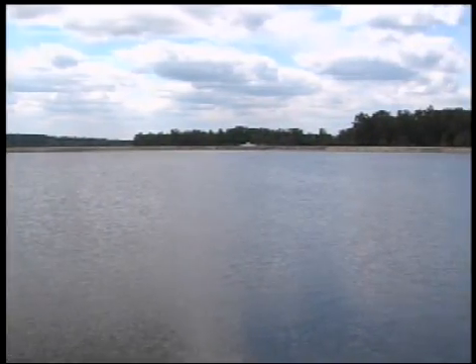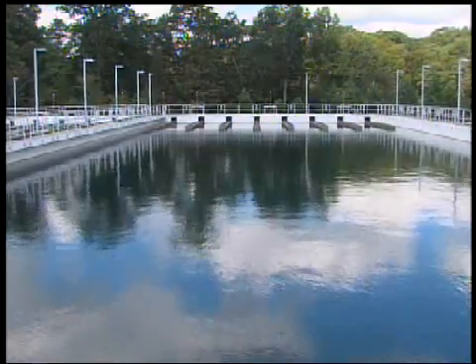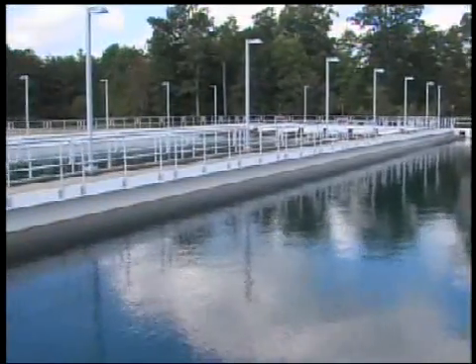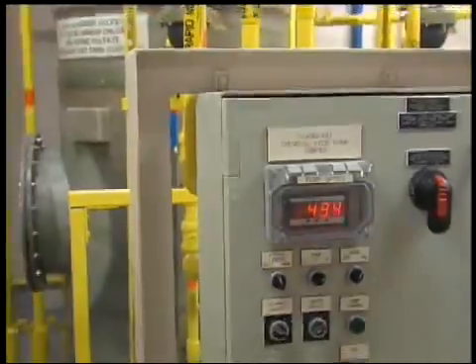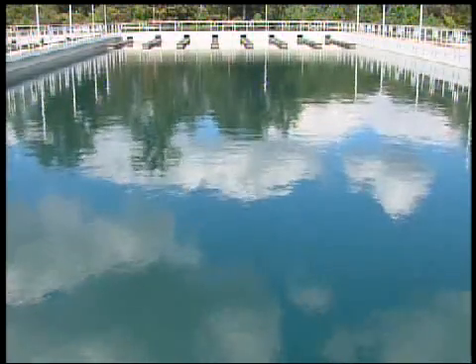The Swan Plant can treat up to 25 million gallons a day from the raw water reservoirs. The water is sent to these two treatment basins. A coagulant called alum is added to make dirt and other foreign particles in the water stick together. The water is then slowly mixed in a process called flocculation. Clumps called floc are formed as these particles stick together and get larger.